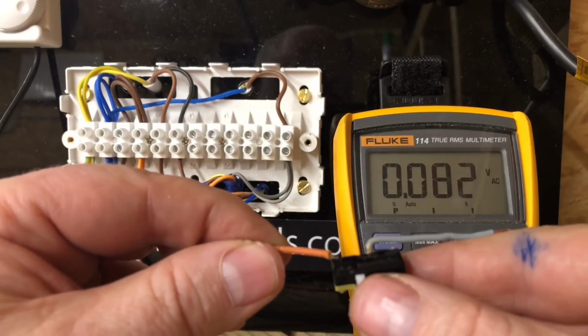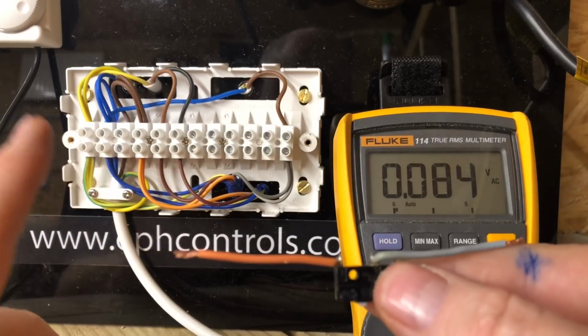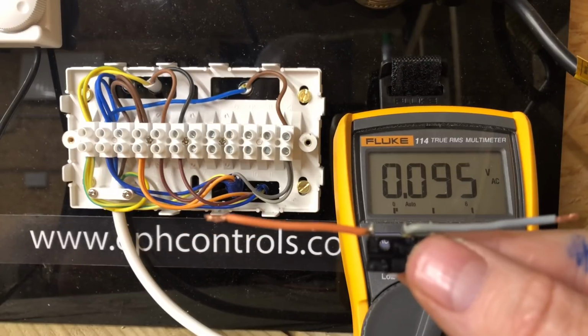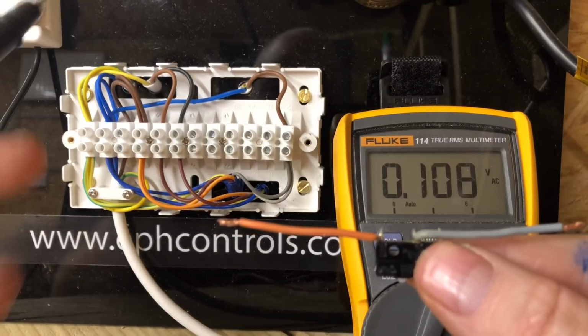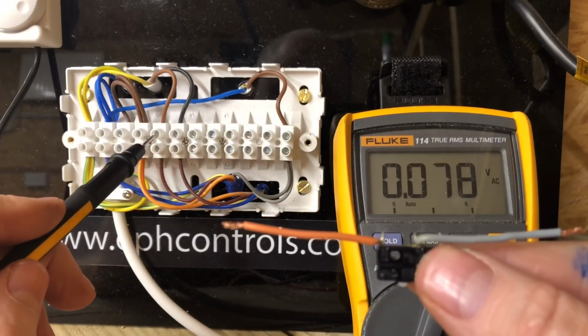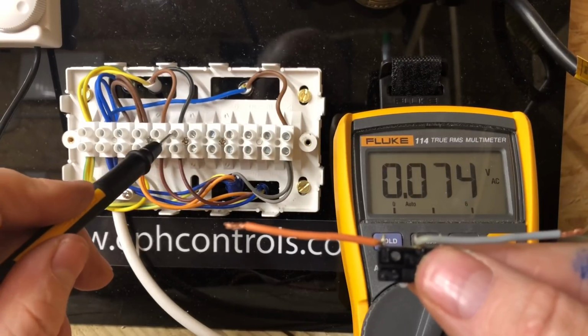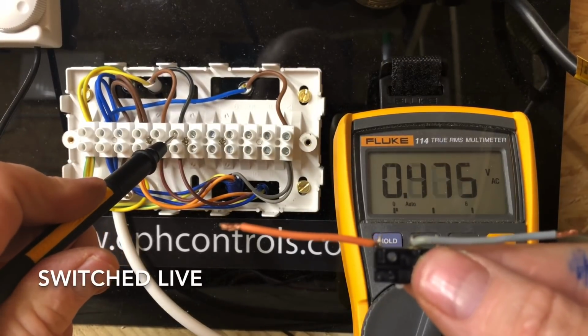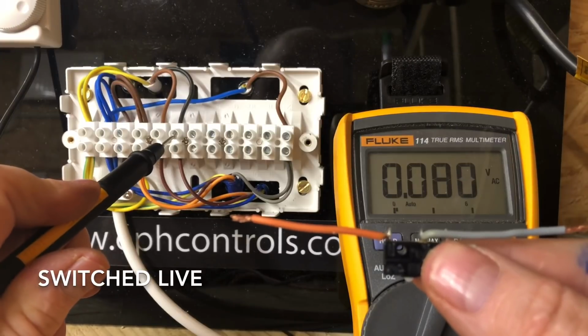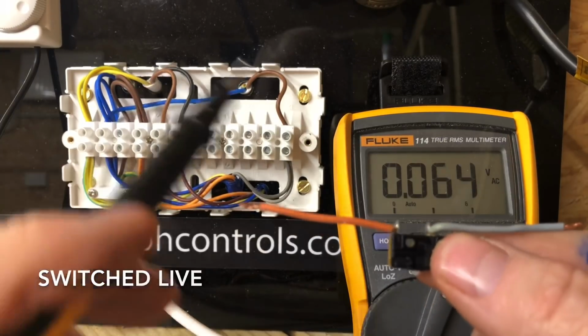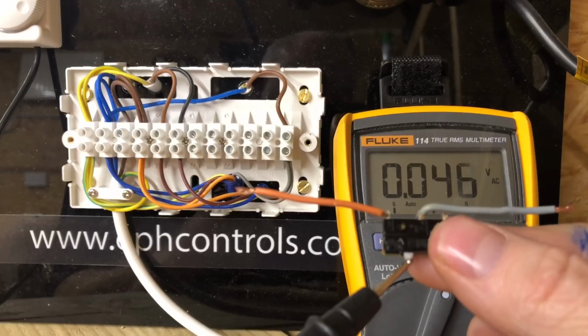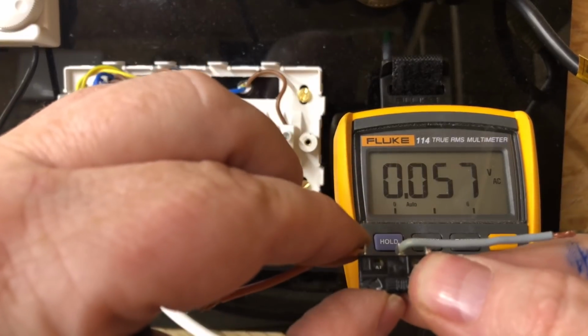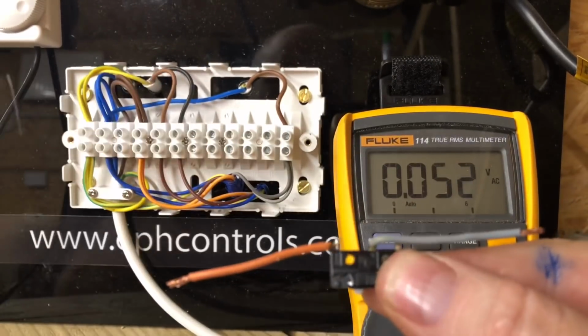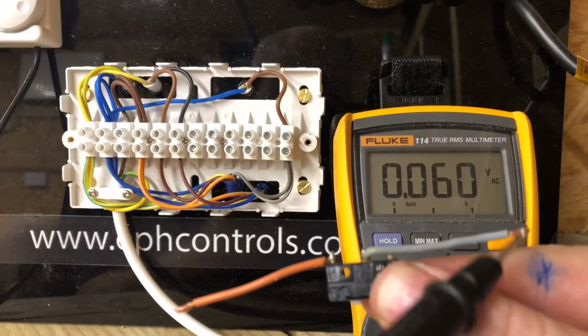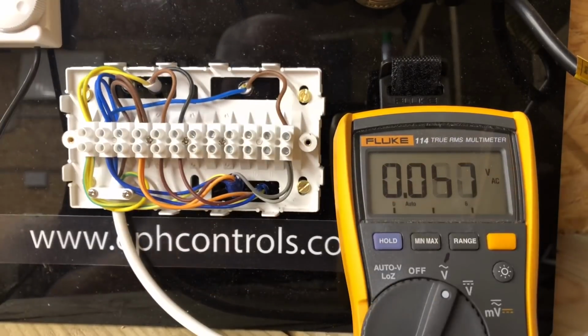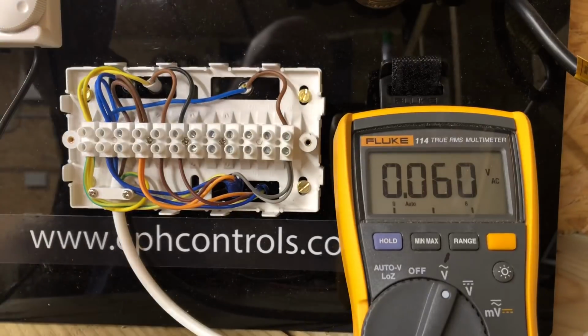So what we need to do is, if we now put demand onto the clock, down one of these, whichever one it is on here, we'll get permanent live. Then once we get permanent live down here, that will open the motor. The motor in the valve will push that micro switch, and then it's going to send us 240 volts down this grey here. So I'll just put demand on now.